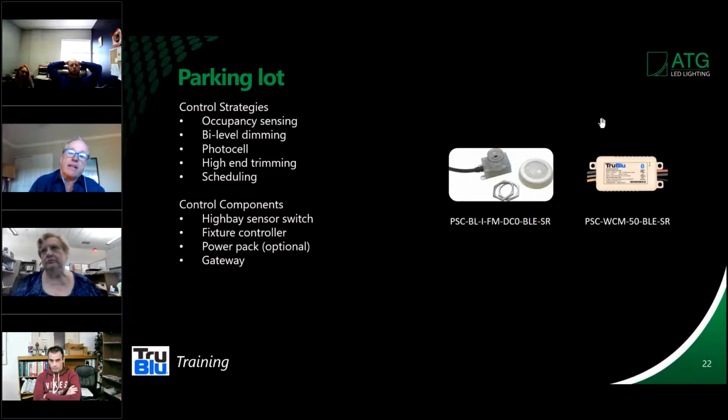So essentially, this device by itself is not IP65, but it will be when it's put inside a fixture that's IP65. And the other thing about this product, and I think we talked a little bit about it, it's on the data sheet, is let's say that the area light in question does not have room, or for whatever reason you can't install this sensor in the fixture. You can have this in an IP65 rated box, which will mount to the pole. So in this case, you can still employ the strategy.